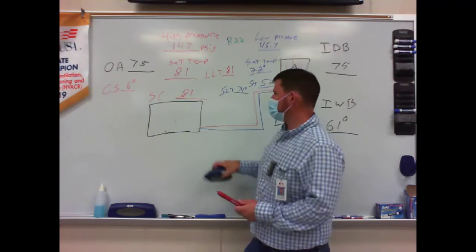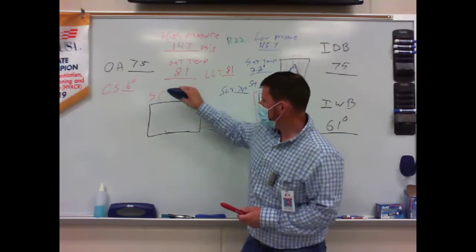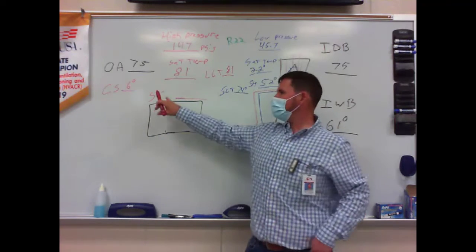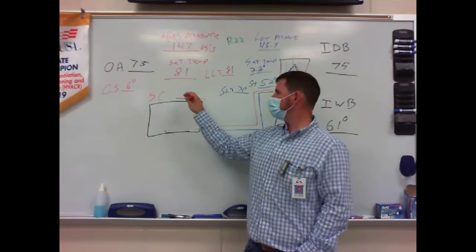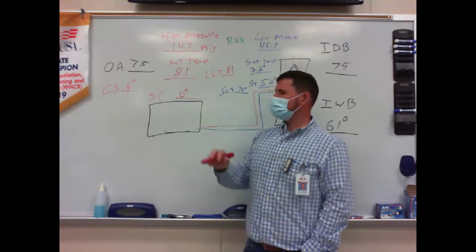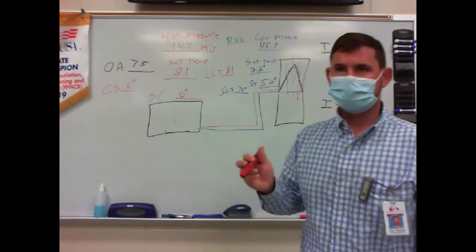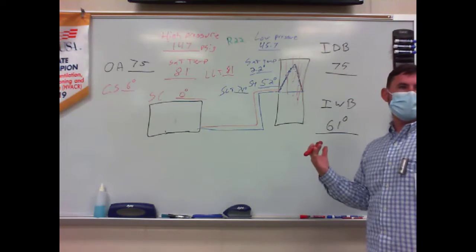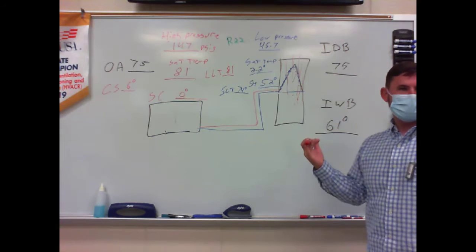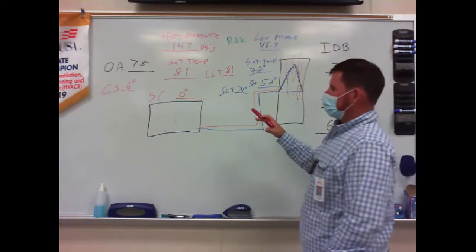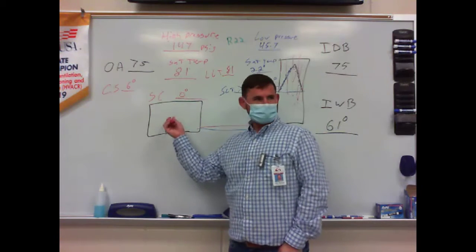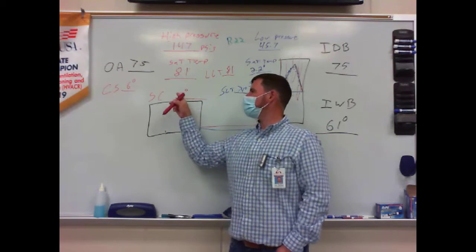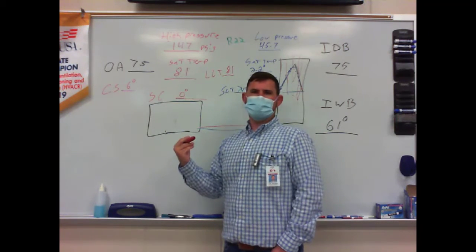My line temperature was 81. So how much did I subcool? 0 degree subcooling. Why did I not subcool any? All right, but why, when I'm undercharged, why is my subcooling low?